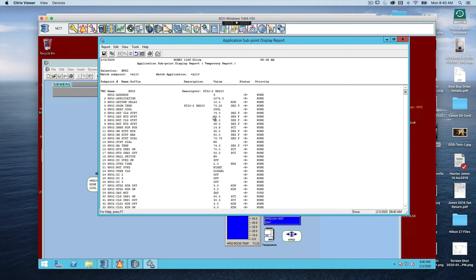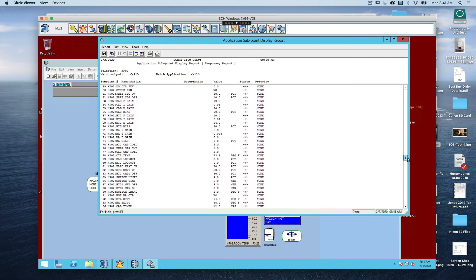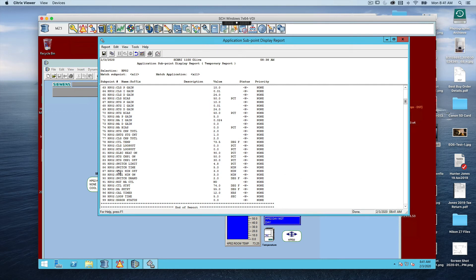The way this application works: when the room reaches 74 degrees it turns on the cooling compressor and calls for cooling; when the temperature drops to 68 degrees the device turns on the heating compressor and heats the room. These values — 74 and 68 — are based upon point number 92 in this report, which is the control set point. Scrolling down to point number 92, the control set point shows we're attempting to control this room to 74 degrees. The current room temperature is 73.25, which is why neither the heating nor cooling compressor is running.